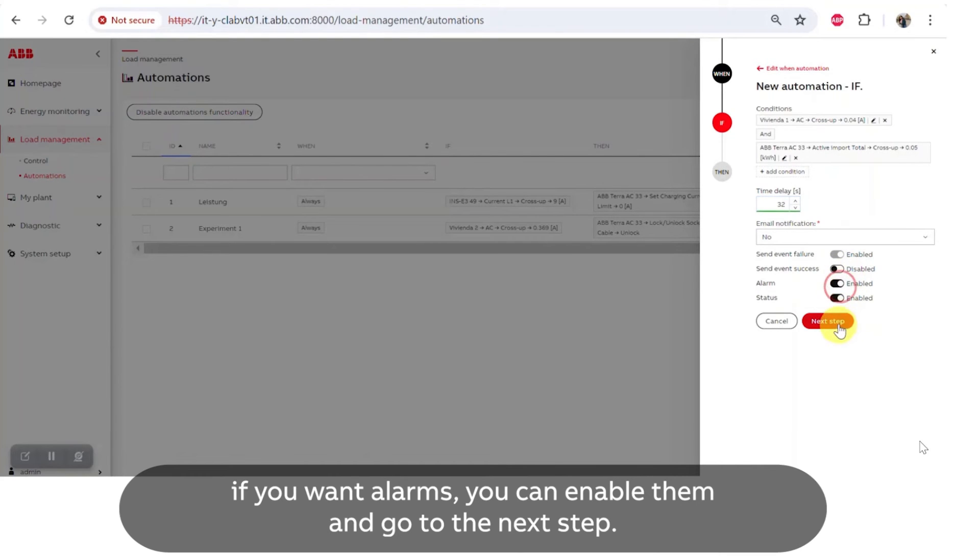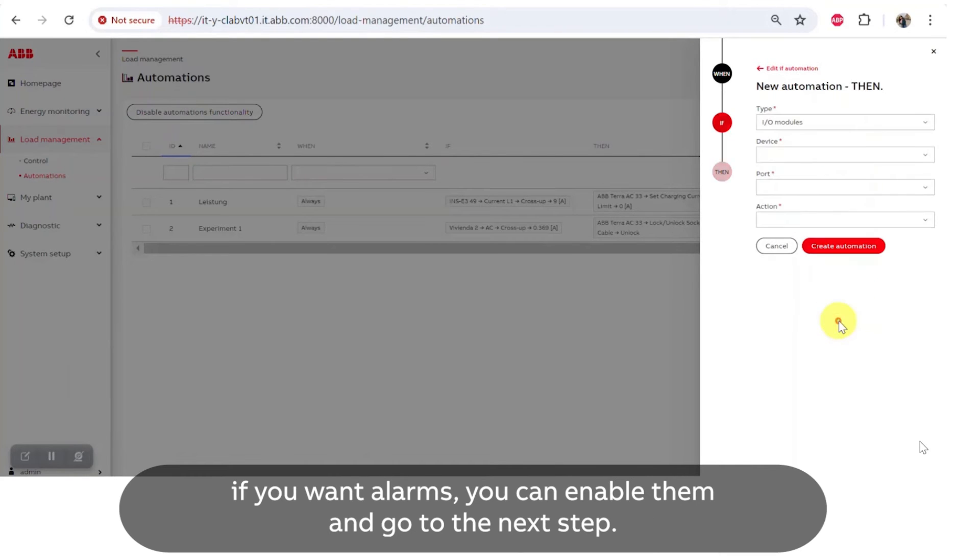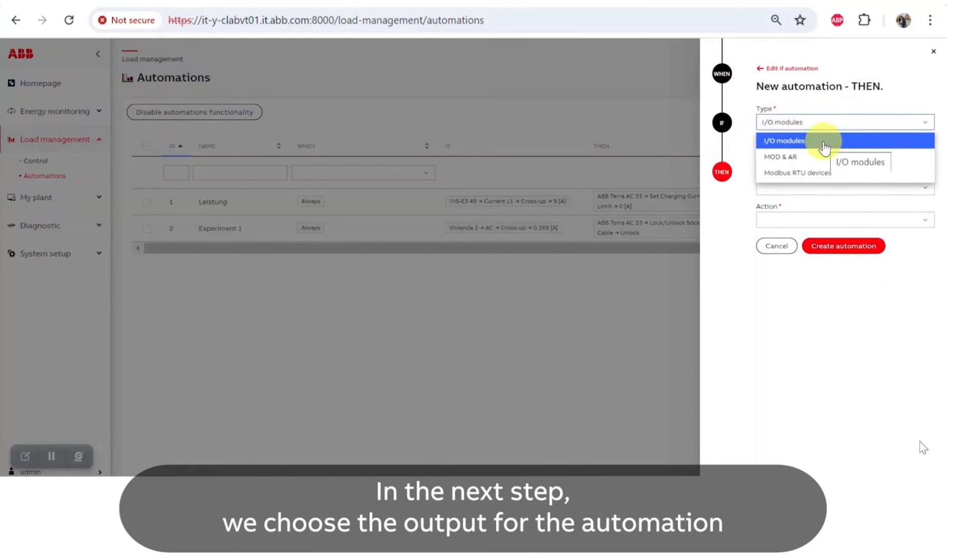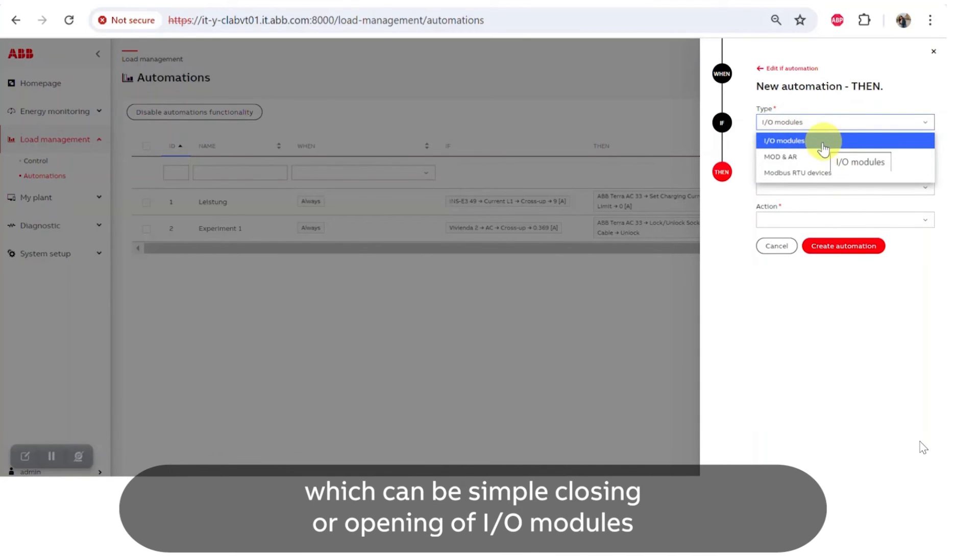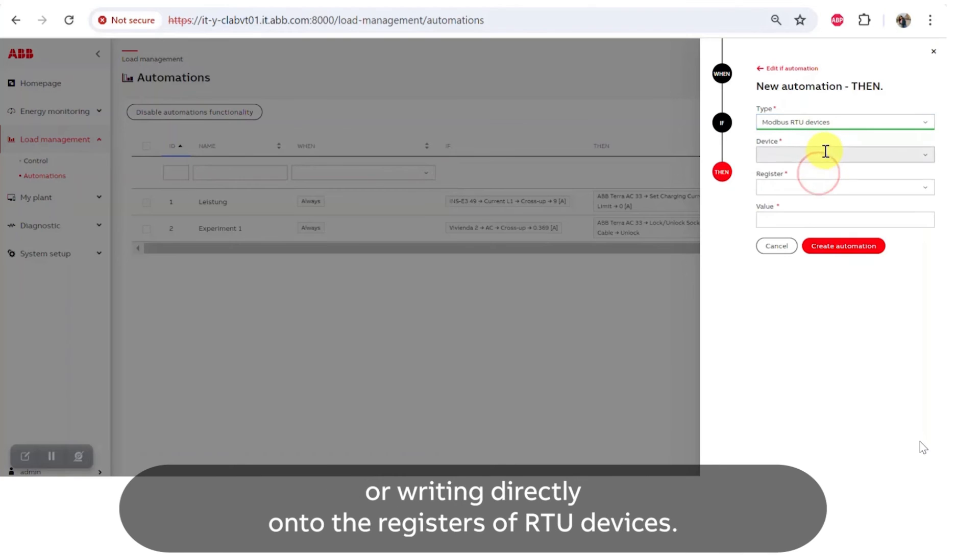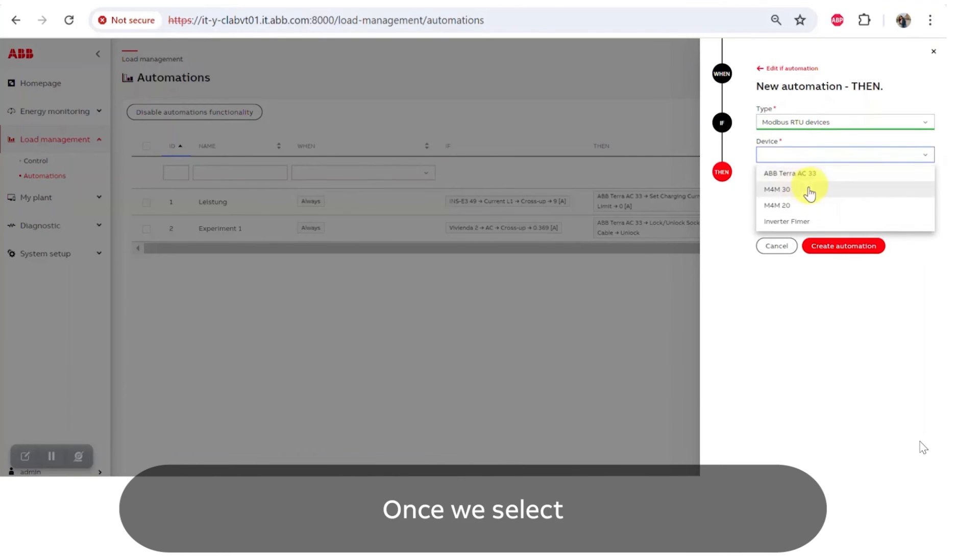In the next step we choose the output for the automation, which can be simple closing or opening of I/O modules, operating the Modbus or RS devices that are connected to SCU200, or writing directly onto the registers of RTU devices.